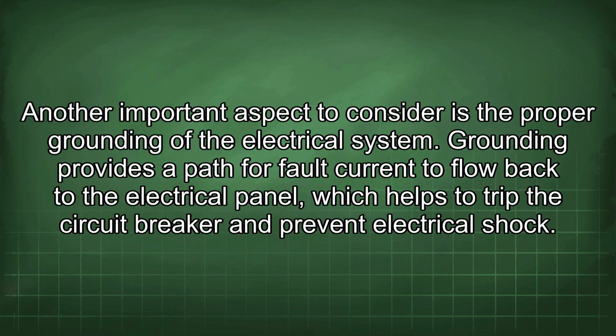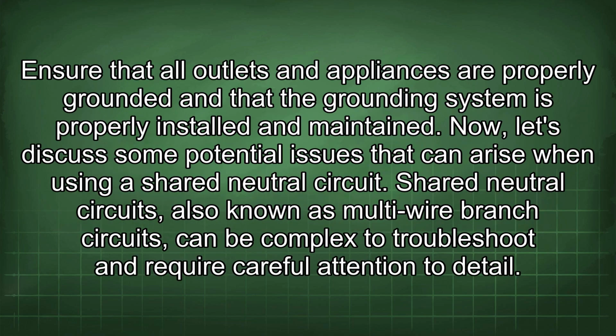Another important aspect to consider is the proper grounding of the electrical system. Grounding provides a path for fault current to flow back to the electrical panel, which helps to trip the circuit breaker and prevent electrical shock. Ensure that all outlets and appliances are properly grounded and that the grounding system is properly installed and maintained.